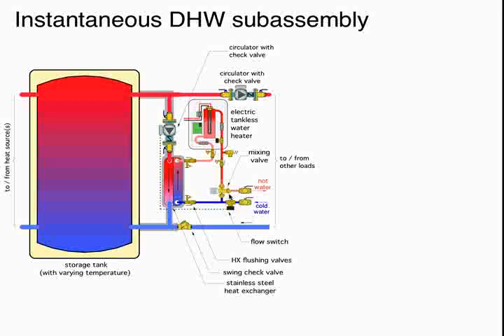This is a critical component here, this ASSE 1017. I'm not sure if that's a current standard or not, but ASSE 1017 or a more modern version of that standard for the anti-scald mixing valve. We don't want to send 160-degree water off to somebody's faucet. Okay. Now, if the tank was only at 80 degrees, this water might come in at 50 and it might get preheated up to maybe 70 or 75 degrees. That's where the auxiliary heater would top it off.